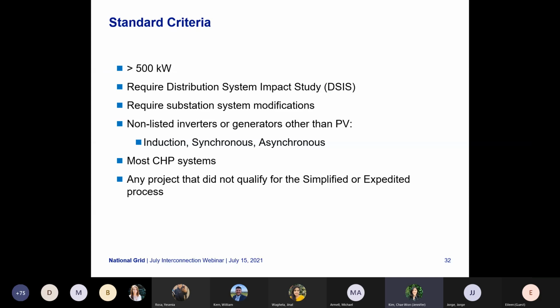So what projects fall under the standard criteria? Any projects greater than 500 kilowatts would automatically fall into this criteria. There's also other items such as requiring a distribution system impact study, requiring substation modifications. If your generator is a non-listed inverter, such as induction, synchronous, or asynchronous, most CHP systems, and essentially any and all projects that would not qualify for the simplified or expedited process.